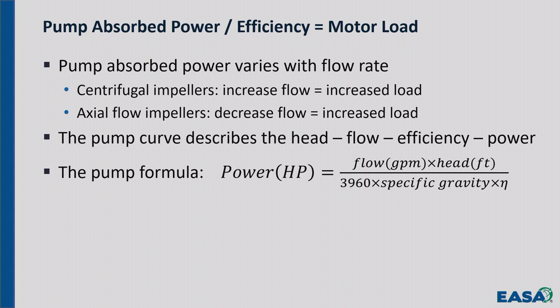You also have a pump formula, which I think everybody working around pumps should know. This is the pump formula. Power, if you're in U.S. units, is in horsepower, flow is in gallons per minute, head is in feet, and head is analogous to pressure. It's how high a column of liquid you have. If you know what the density of the liquid is, it's going to have a certain pounds per square inch pressure at the bottom of it. So when I say head, we're just talking basically about pressure for a specific liquid.